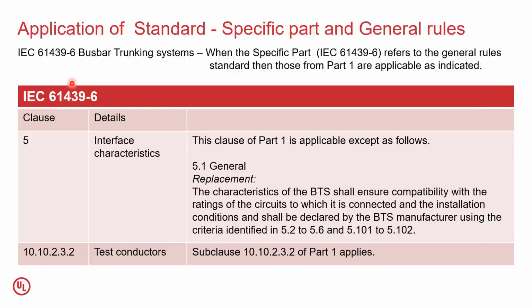One more example. If you go to 61439-6 and go to a specific clause, 10.10.2.3.2, the subject title is test conductors. The -6 does not contain any information about the test conductors. What it does is send us back to part 1. It says subclause 10.10.2.3.2 of part 1 applies. So this is what you will do. When you go to the test conductors, there is no information in -6, but it says you need to apply this particular information from part 1. So this is how you typically start referencing back and forth.